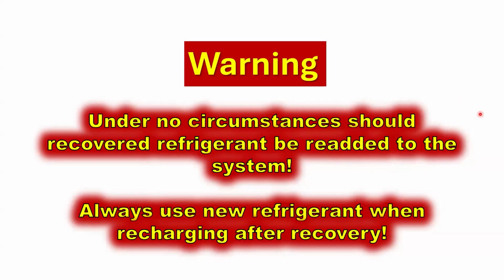There's a whole bunch of good reasons to use new charge. You don't know the recovery tank you're pulling that out of. You don't know the condition of it. You get those recovery cylinders back and you don't know if they're clean. There have been cases where they're not clean, right? There's debris and all types of stuff, oil in the recovery cylinders. So unless you have a brand new recovery cylinder, which I'd still question, I'd still always do a vacuum on it. But you're pretty safe on a new recovery cylinder.